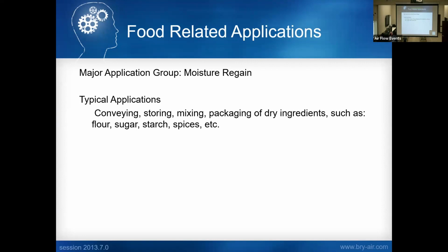The smaller the rotor, the smaller the reactivation, the lower the energy. So that's something our applications engineers look at: what do I need to dehumidify, what do I need to cool, and do it with the most practical system. And in this case, it's a constant bypass. So either we'll bring the air all into one common return, bypass a certain portion, or in some cases, we have two separate returns.